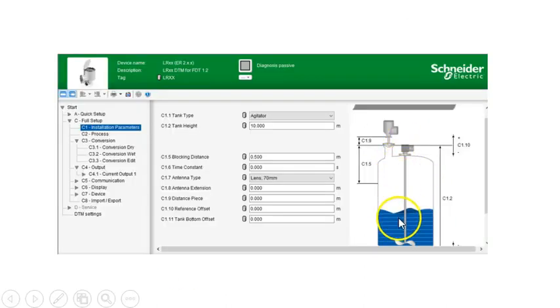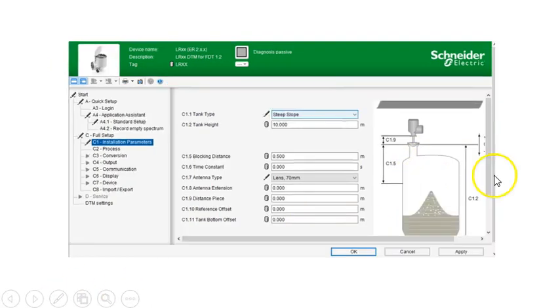So when we work with a liquid level measurement, usually a reliable measurement can be had with one single pass. But when we work with solids, that's not always the case. Remember, the reflections are often weaker. We can get some erratic signals mixed up in the echoes that come back because of these different profiles. So what the algorithms do is they overlap several measurements to determine which signal is the true level. Remember, we talked about that averaging. That's what a solids level radar is going to do.